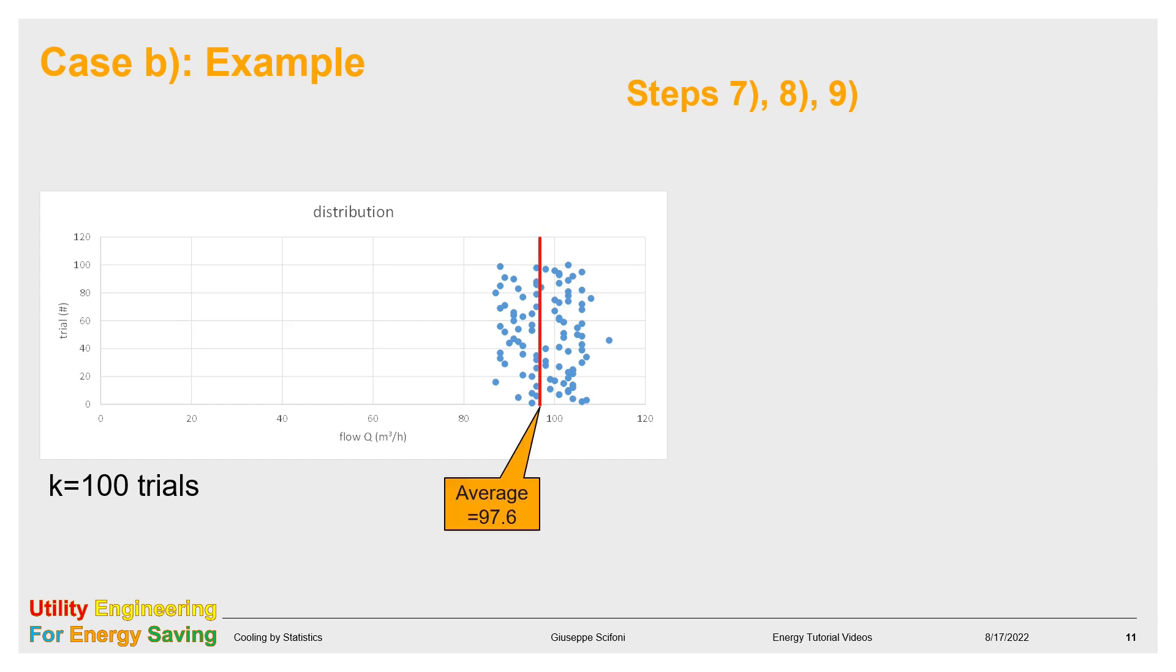Finally, we build the average and the standard deviation of all the found results. The quantity to be used for the sizing is the average plus standard deviation. In the example, we get 103.7 cubic meter per hour, and we have used 100 trials.